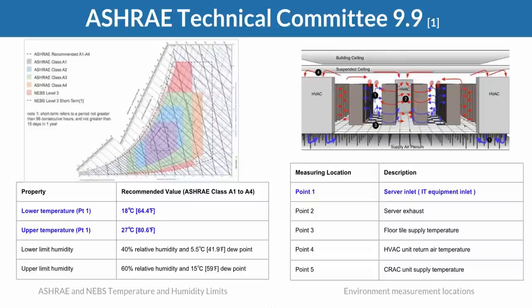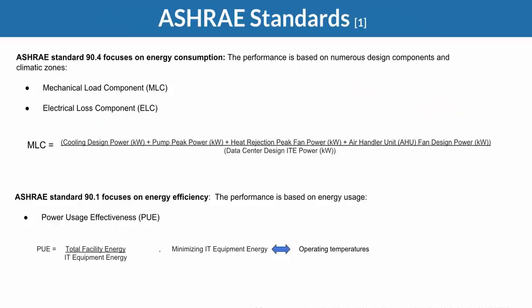But on the other hand, if we are able to properly optimize the system itself and the design of the room, the design of the recirculation patterns within the domain, we could significantly reduce the operational costs for a data center. Some other ASHRAE standards that facilitate this kind of analysis are the ASHRAE 90.4, which focuses on the energy consumption. And one would say, hey, you can calculate these standards based on the general understanding of the design of a data center. I have 50 stacks of servers, I have a room that is that big. Each one of them provides that much power.